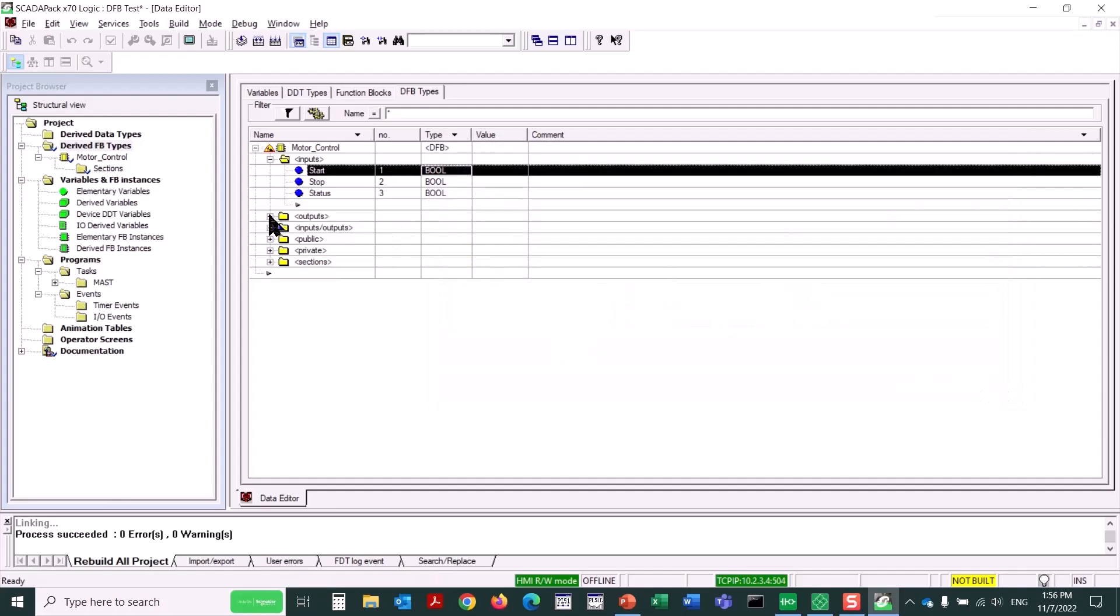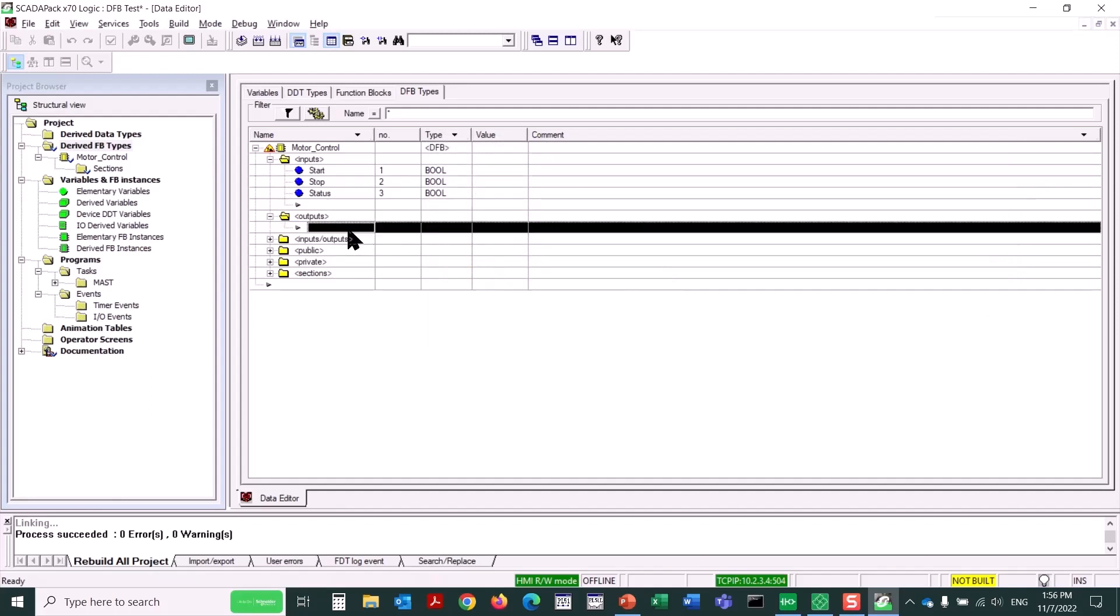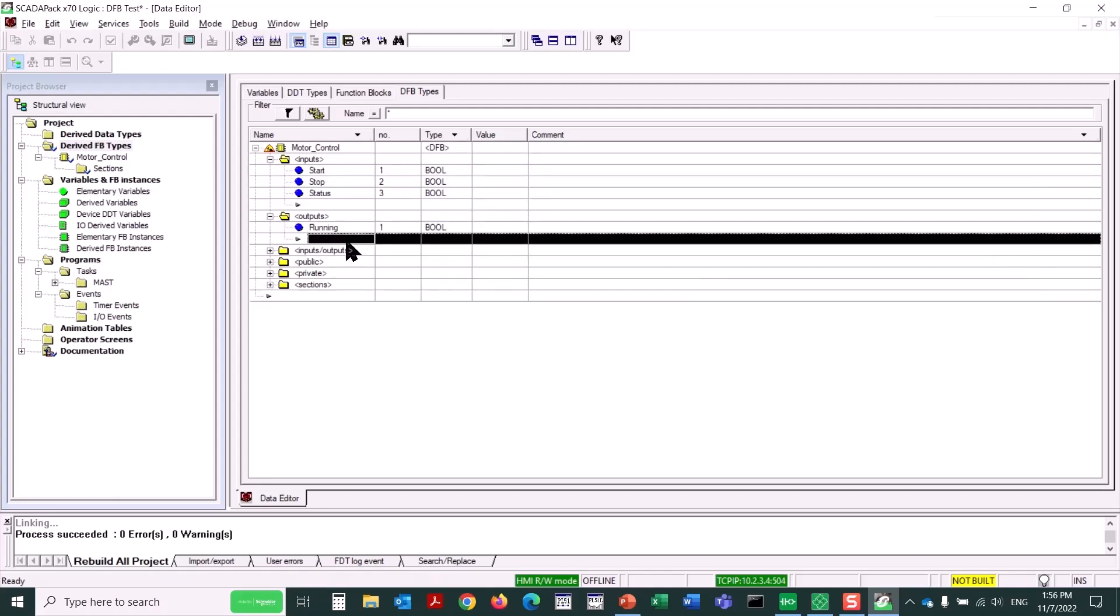Now I'll expand the Outputs category, and we'll add two outputs, one called Running, and one called Aborted. Each of these inputs and outputs will create a pin on the derived function block, either input pins or output pins. The names used are generic, so this DFB can be used in multiple ways.